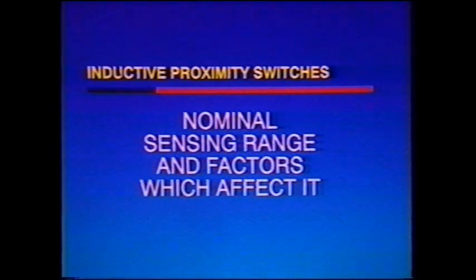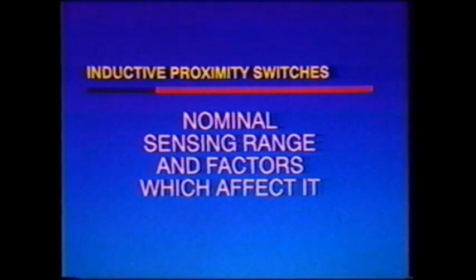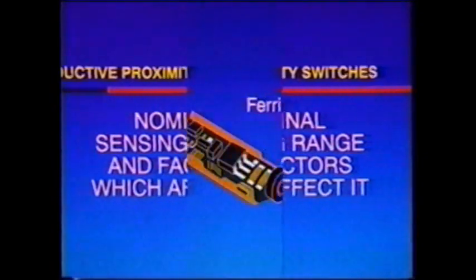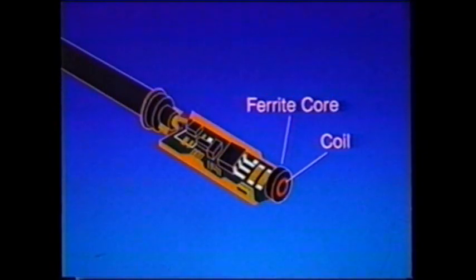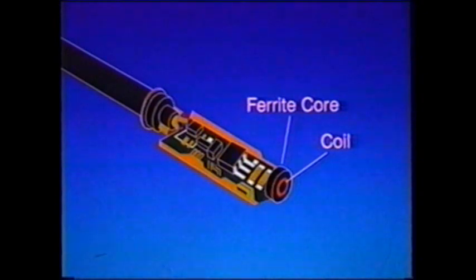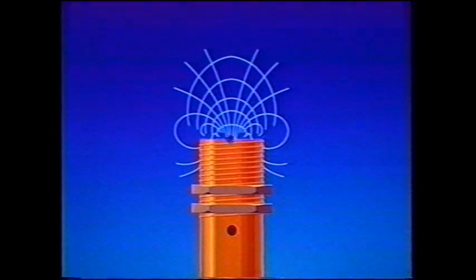Now we're going to look at inductive switches and what you should be aware of when applying them. First is the specified sensing range and the factors that affect it. An inductive proximity switch contains a coil and a ferrite core. Together, these two components form the inductive portion of an LC-tuned circuit, which drives an oscillator. This coil and core set up a very low energy electromagnetic field, which is radiated from the active face of the switch.